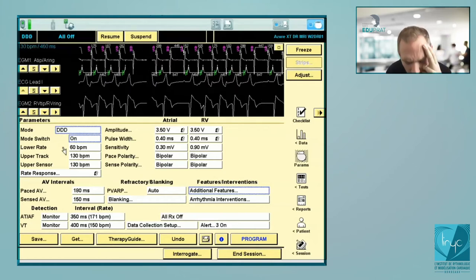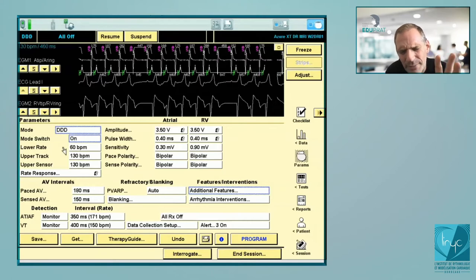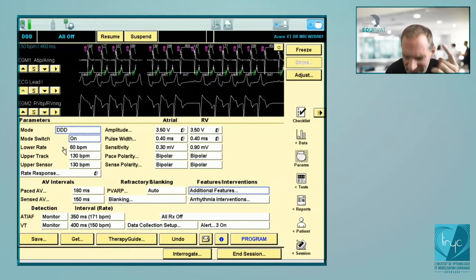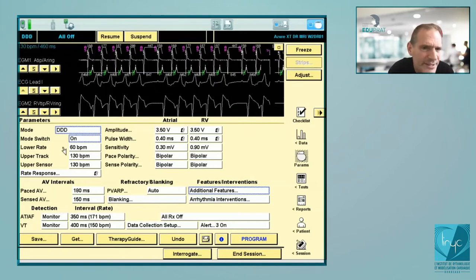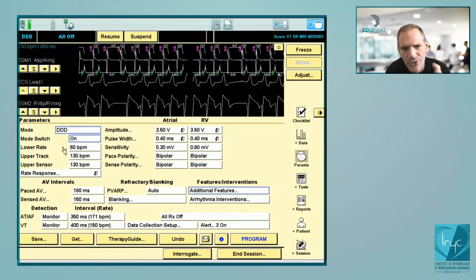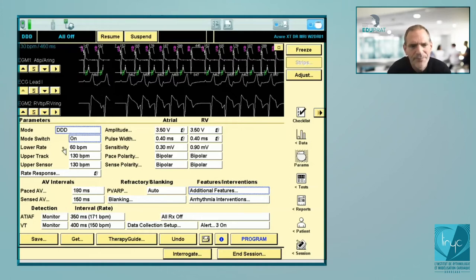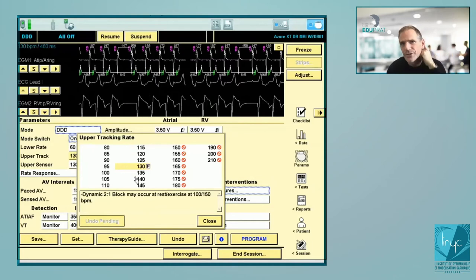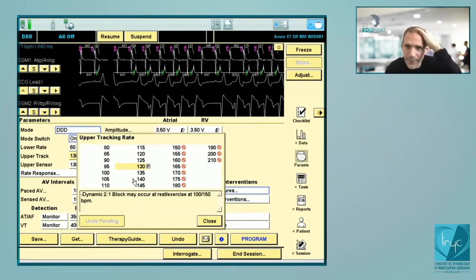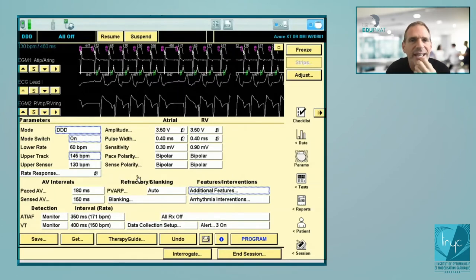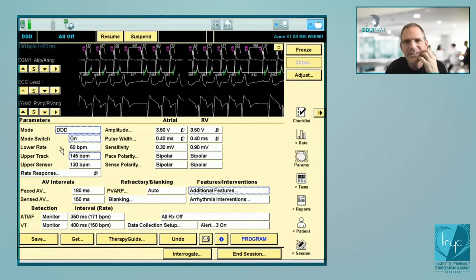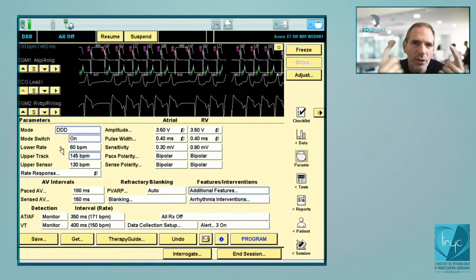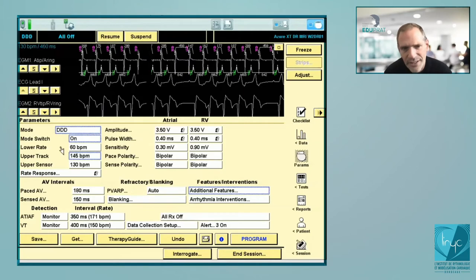If you want to correct Wenckebach behavior, the only solution is to reprogram the upper tracking rate to a faster value. There is absolutely no reason to limit the upper tracking rate if you know the patient has sinus tachycardia and is young and will reach a rate of 160 bpm. You need to reprogram the device to allow a one-to-one relation between atria and ventricle up to a very fast rhythm.